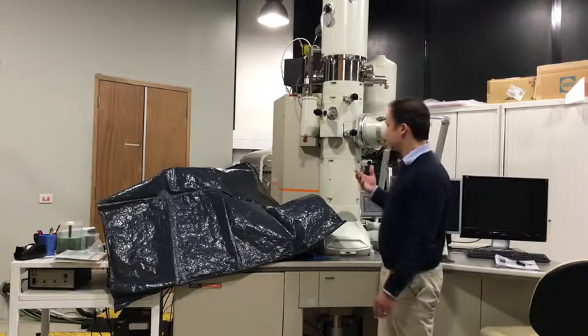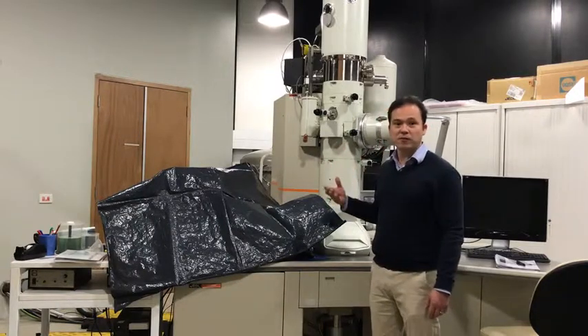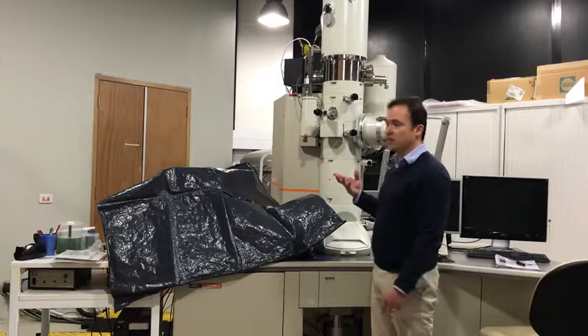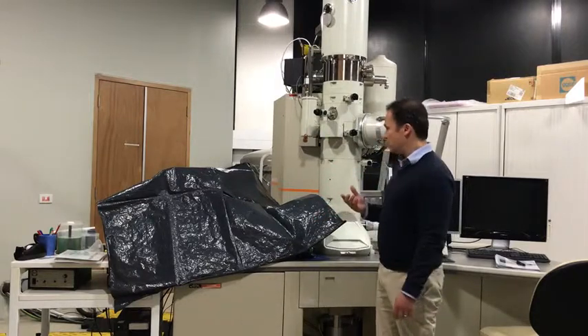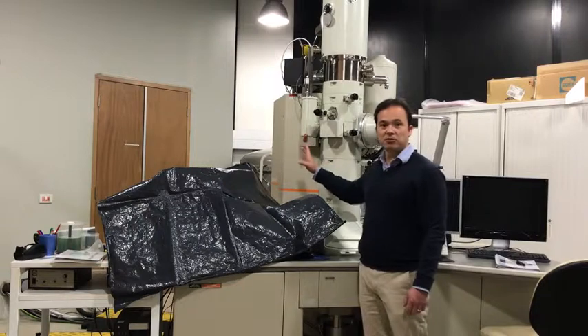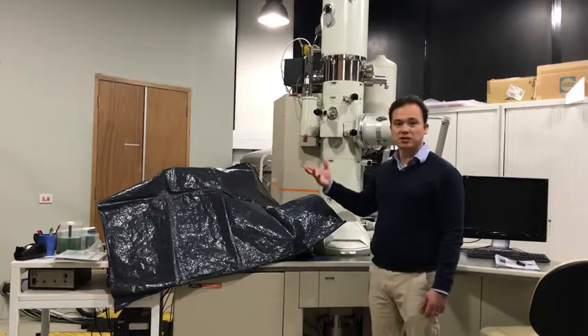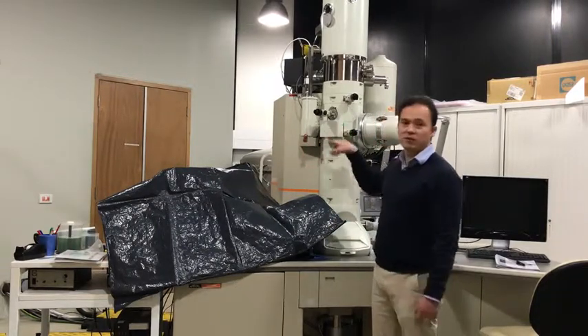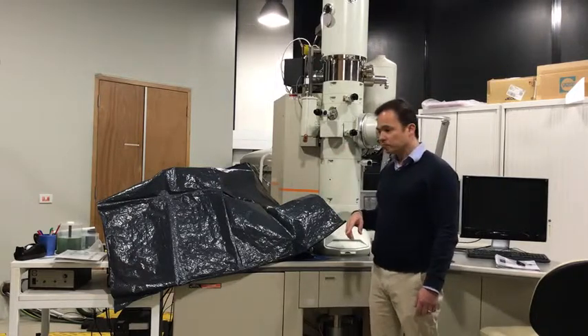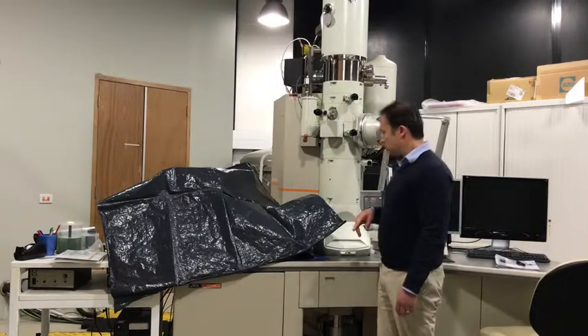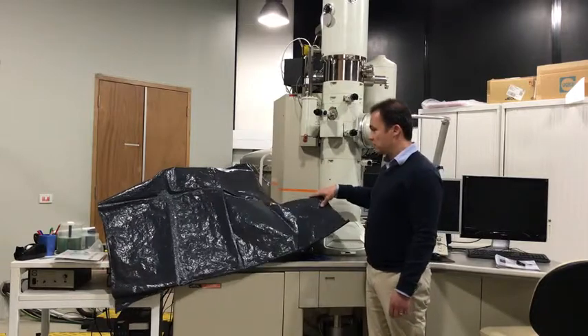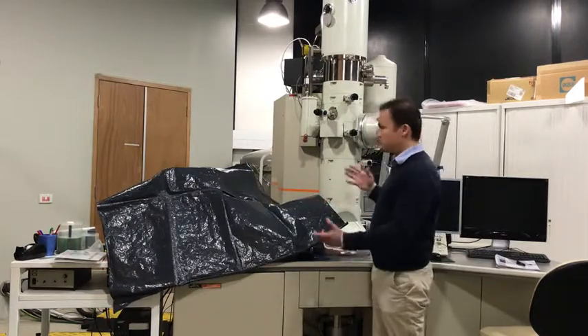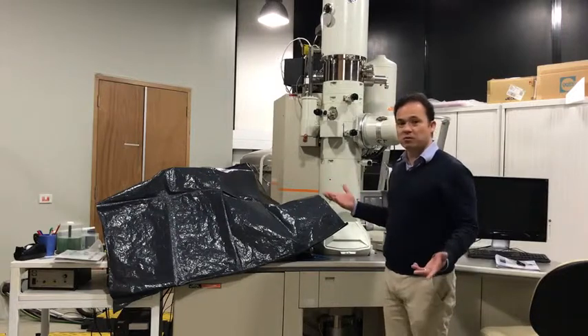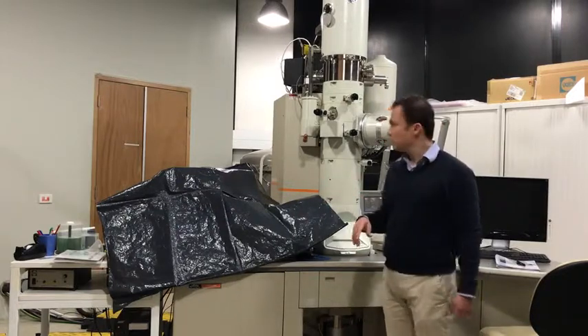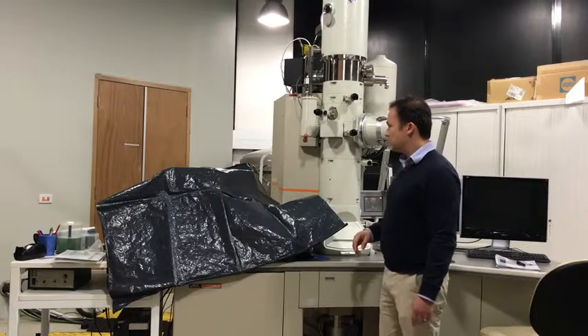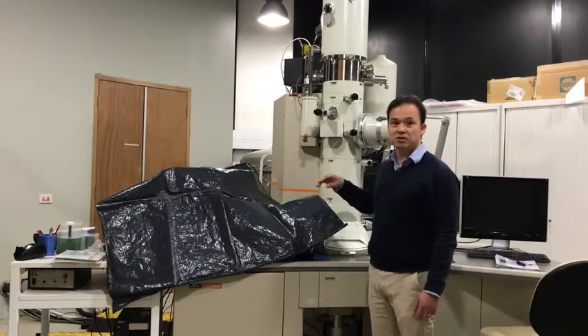anything left in the system, gas, water vapor, and there's always a little bit, because you can never make a perfect vacuum system, will condense out on the cold finger. And at the end of the day, when we run through a heating cycle, that all gets evaporated off and trapped by the other pumps. So this sheet is actually here from the last user. This is the state in which you walk in the morning to use the microscope, and this sheet was left here from the last user because they had to do a cryo cycle.